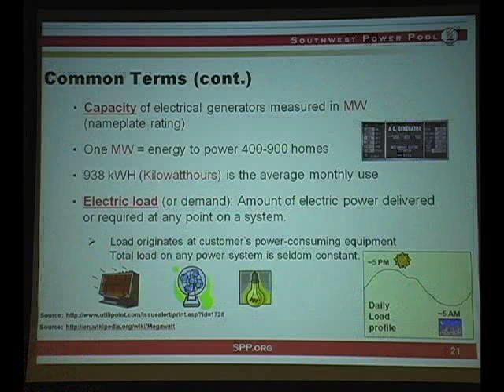A couple terms in generation that are important: you may hear the term baseload generation. Baseload is generation that you essentially put on and run at the same level all the time. It's baseload in that the total electricity demand never falls below that level, so you never need to back it down. If you take the state of Nebraska, let's say we're operating at 5,000 megawatts, we may cycle between 3,000 and 5,000 megawatts during the day. That means we need 3,000 megawatts of baseload, and then 2,000 megawatts of peaking or load-following generation, which fluctuates during the day as the load goes up and down.